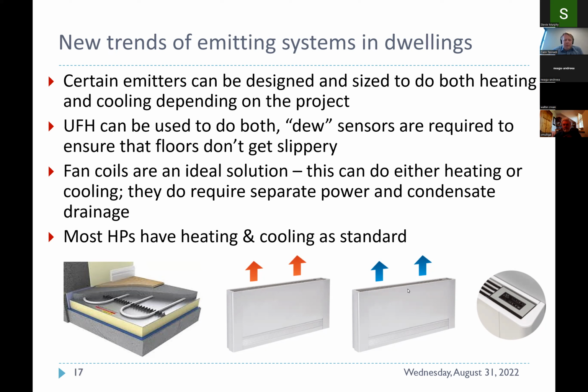Keep in mind, though, that when we use fan coils, this requires a separate power supply, because what we have in it is a fan, a little ventilator, that is forcing the air through a coil through which we're pumping either hot water or chilled water. They have their built-in controls, so they need power supply. And when we do cooling, because of the low temperature that we put through, we're going to have a good bit of condensate being formed. For that reason, we have to make sure that we put in a condensate drainage.